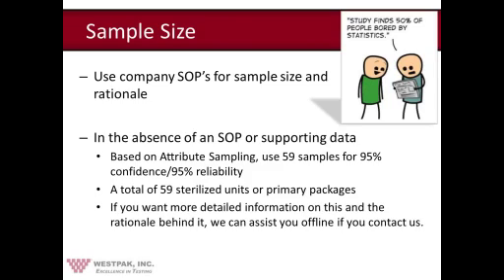But oftentimes clients don't have this information and they ask us for guidance. If you ask a statistician about this, the answer they usually give you is it depends. It depends on the confidence, the severity of what you're looking for, how conservative you want to be, what your process is, whatever. It just depends, and usually that isn't too helpful. So when people ask us this question, for this type of package validation testing, our recommendation would be 59 samples for 95% confidence and 95% reliability in the absence of other data. This is based on attribute sampling, so that is a total of 59 sterilized units or primary package. If you want more detailed information on this, we can assist you with the rationale offline if requested. Herb, is there anything else that you wanted to speak on about this?